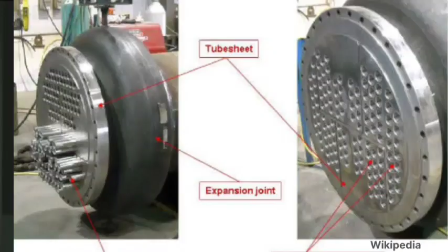Just I have some drawing questions, like for this tube sheet - there is a tie rod, right? The tie rod, how much should it be inserted? 1.5 times of the diameter. Okay, so now suppose the tube sheet thickness is 100 mm.